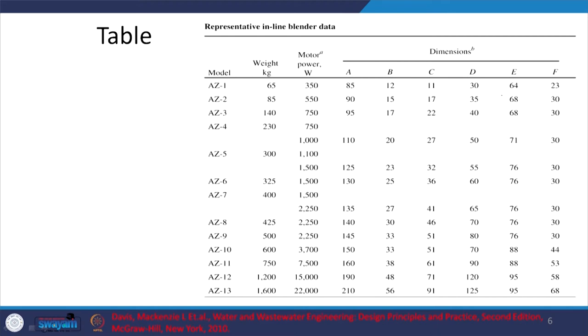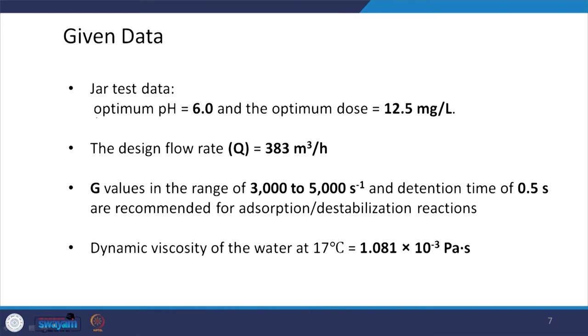We have an inline blender with different dimensions. We want to get our relevant G and theta values — that is what we are concerned with at the end of the day. I have the motor power given, so I can choose one motor as a trial. From the jar test data: pH is 6, optimum dose and flow rate are given. For charge neutralization based adsorption and destabilization, theta is less and G is relatively higher. The temperature is relevant because viscosity of water changes with temperature, and the viscosity at that particular temperature is what we have.